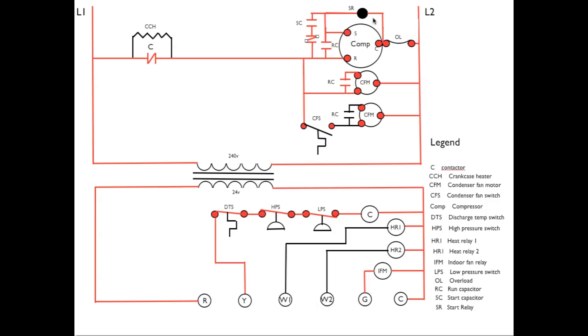This is a very high voltage relay coil. When the voltage gets high enough, then it will energize and open this set of contacts. I will go through the way the start relay works in another video, but this is a potential start relay, or we just call them potential relays. The power is also passing through OL, which is a line break overload.